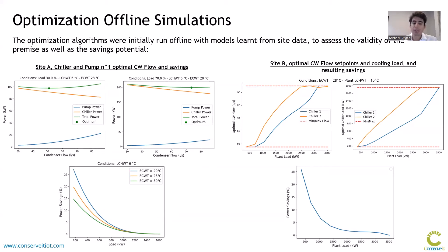These show quite high savings potential. On site B on the right, we see a case with two chillers running simultaneously in simulation, with the load per chiller and condenser flow per chiller showing the optimum for different values of plant load. For different plant loads, there are different optimums for each chiller for both the load and the condenser water flow. Optimizing all of this together holistically, the bottom right shows the potential power saving percentage, which is also quite high.